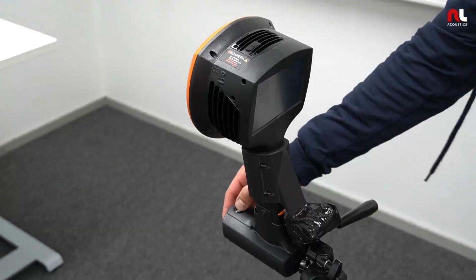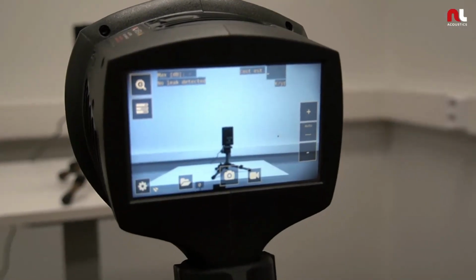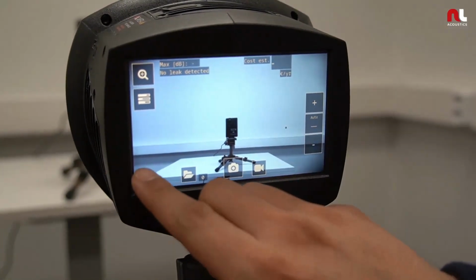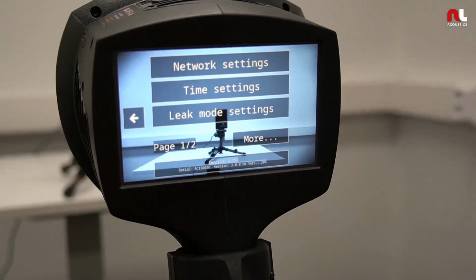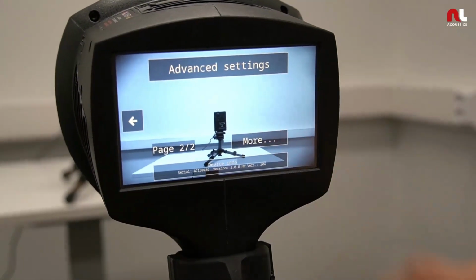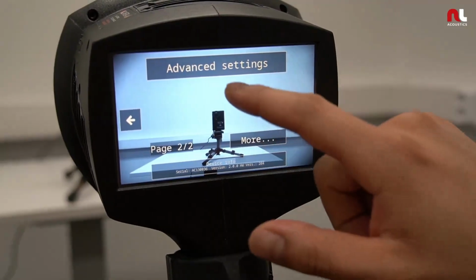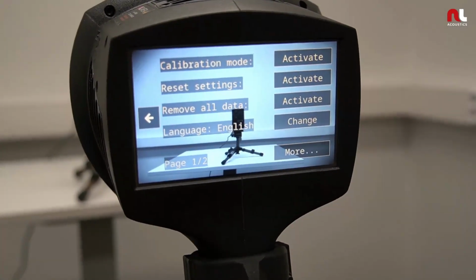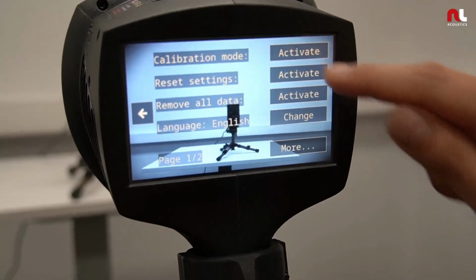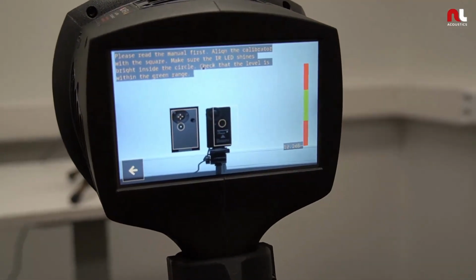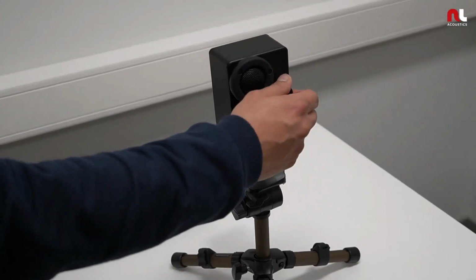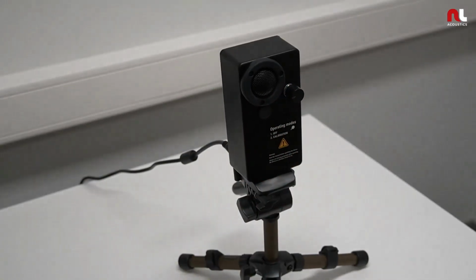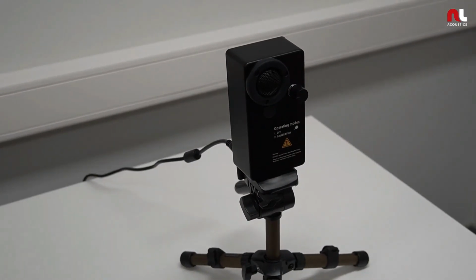Power your acoustic camera. On the camera screen, tap the cogwheel icon at the bottom left corner. Tap More until you see Advanced Settings. Choose that. Tap the button next to it that says Activate to turn on the calibration mode. Plug in the Sonic Tester and turn it on to the calibration mode. The device takes about 10 seconds to start.